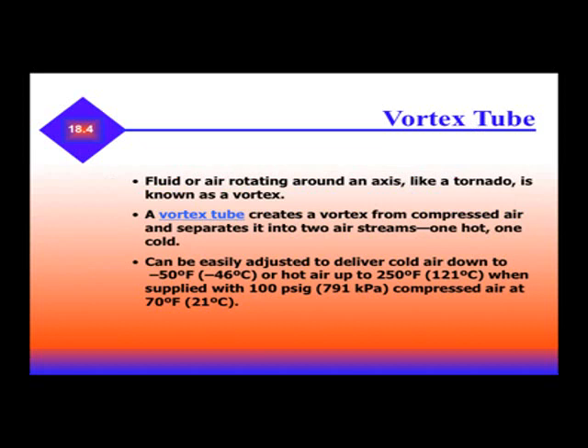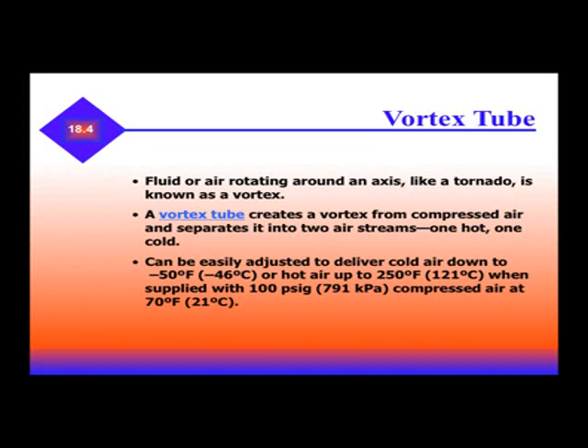The next type of refrigeration we're going to talk about is a vortex tube. Fluid or air rotating around an axis like a tornado is known as a vortex. A vortex tube creates a vortex from compressed air and separates it into two air streams, one hot and one cold. It can be easily adjusted to deliver cold air down to negative 50 degrees or hot air up to 250 degrees when supplied with 100 psi compressed air at 70 degrees.